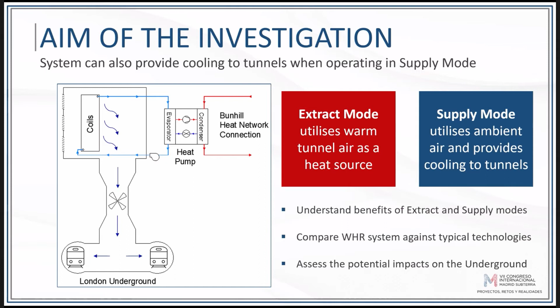So just to explain briefly some of the modeling work that we've done. As part of my PhD, I developed a model using a tool called Engineering Equation Solver. And this model is able to calculate the efficiency of the waste heat recovery system based on temperature and humidity data, either for ambient air, if you're dealing with supply mode, or tunnel air, if you're dealing with extract. So one of the main elements, particularly when considering the cooling aspect, is condensation, particularly when we're using ambient air, which has quite a high moisture content. Condensation is a big issue.